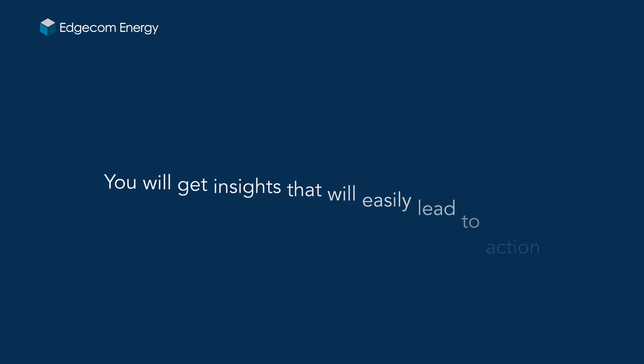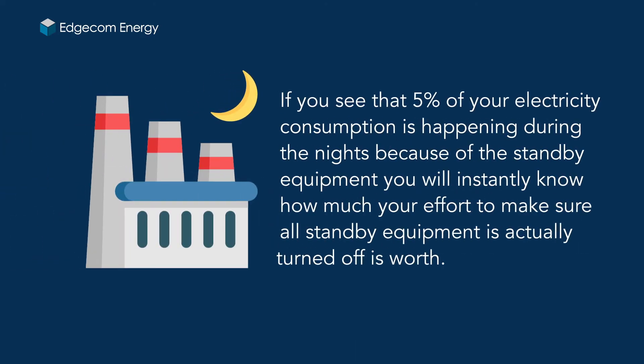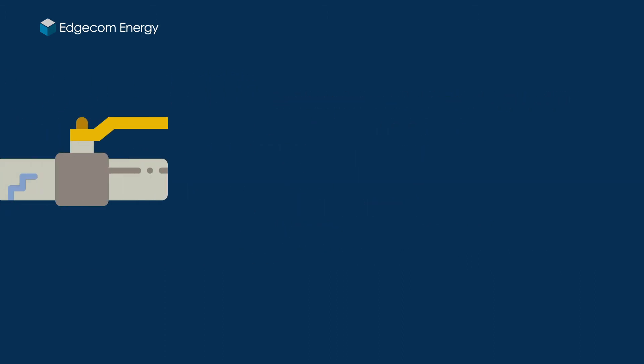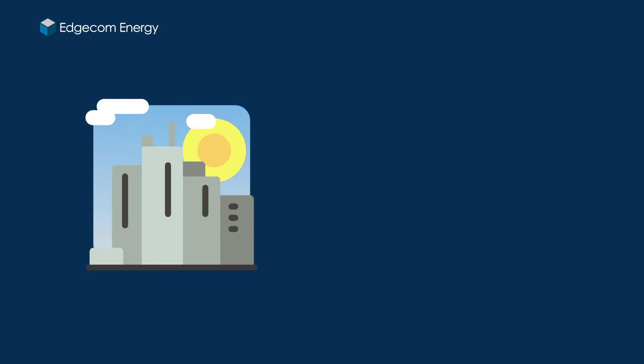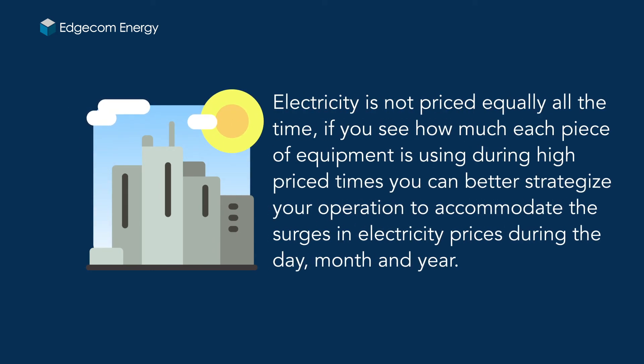Let's see three real-life examples. First, if you see that 5% of your electricity consumption is happening during the night because of standby equipment, you will instantly know how much your effort to make sure all standby equipment is actually turned off is worth. Second, if you see that during nighttime you are consuming a weird amount of water, you'll know that there is probably a leak. Third, electricity is not priced equally all the time — if you see how much each piece of equipment is using during high-priced times, you can better strategize your operation to accommodate the surges in electricity prices during the day, month, and year.